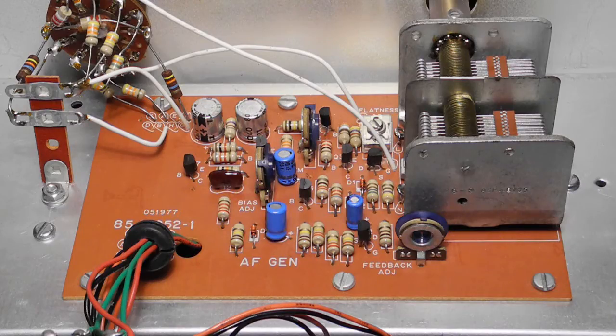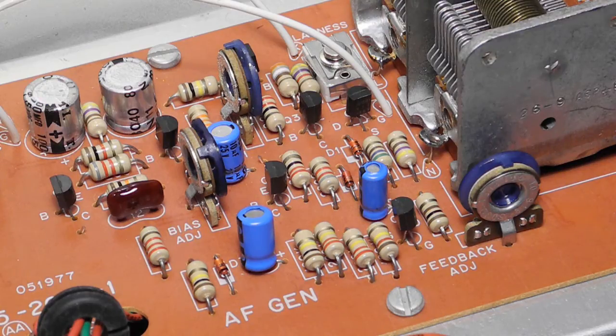The unit is solid state using 7 transistors, 2 of which are field effect transistors. The oscillator uses a differential amplifier oscillator where the frequency is controlled by a notch filter with values determined by the frequency control and range switch settings. The square wave section uses the same oscillator, followed by a Schmitt trigger, amplifier, and emitter follower. There's 1 trimmer cap and 3 trimmer potentiometers which need to be adjusted during calibration. Calibration requires a voltmeter and optionally an oscilloscope.